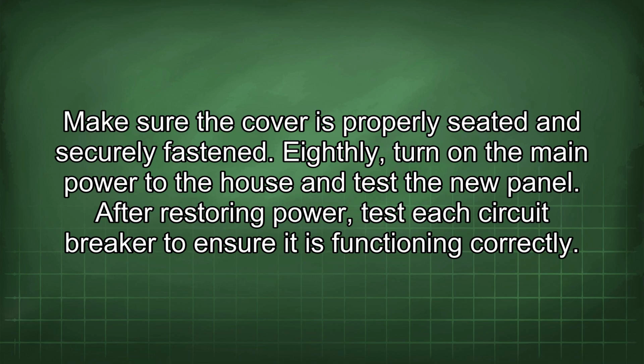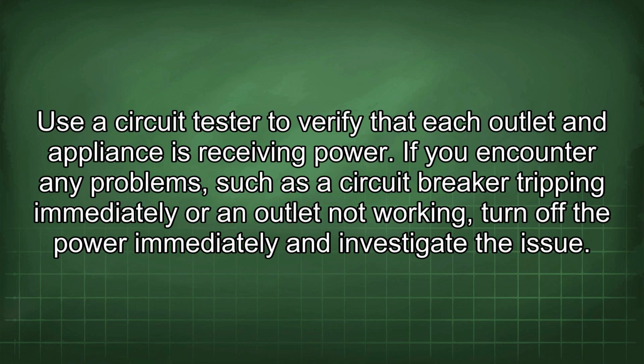Eighthly, turn on the main power to the house and test the new panel. After restoring power, test each circuit breaker to ensure it is functioning correctly. Use the circuit tester to verify that each outlet and appliance is receiving power. If you encounter any problems, such as the circuit breaker tripping immediately or an outlet not working, turn off the power immediately and investigate the issue.